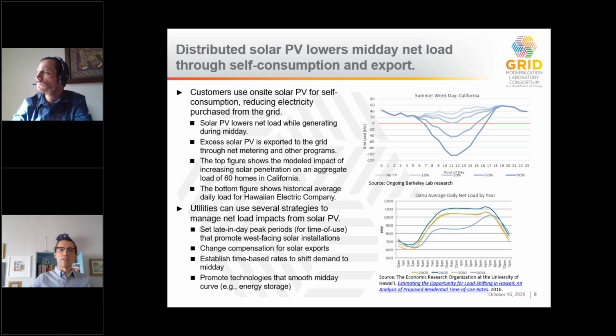Starting with solar, the primary impact of distributed solar PV is lowering building net load through self-consumption and net export. Self-consumption offsets customer consumption from the grid through on-site generation, but once the site's net load reaches zero while solar is generating electricity, excess solar PV is exported to the grid. The figure here shows the increasing impact of adding solar to individual homes. While some homes with solar are exporting during midday even at low penetrations, it becomes evident that higher penetrations reveal a negative aggregate net load.